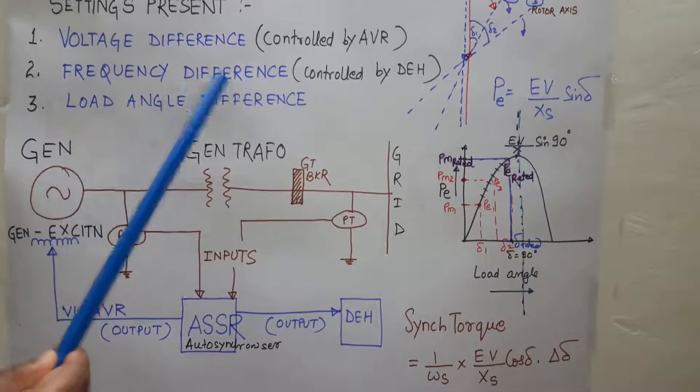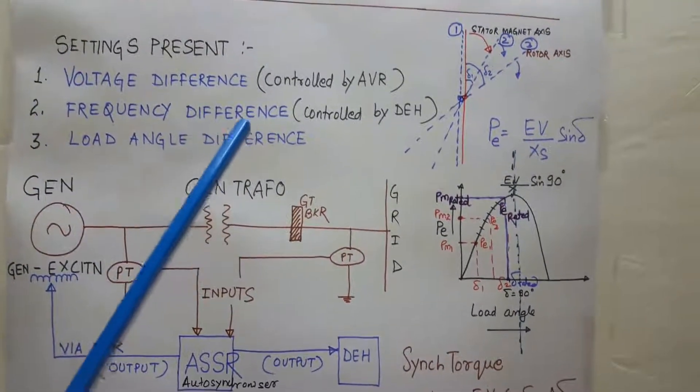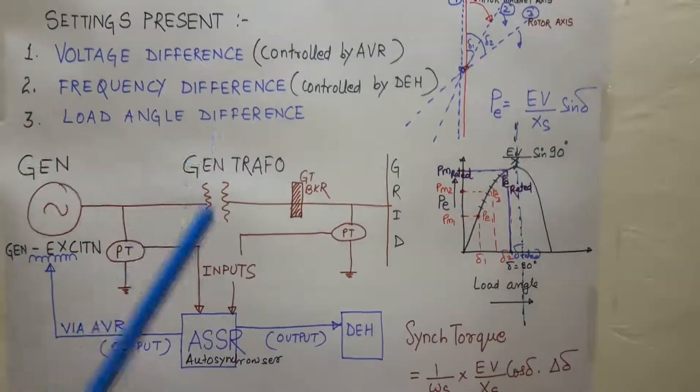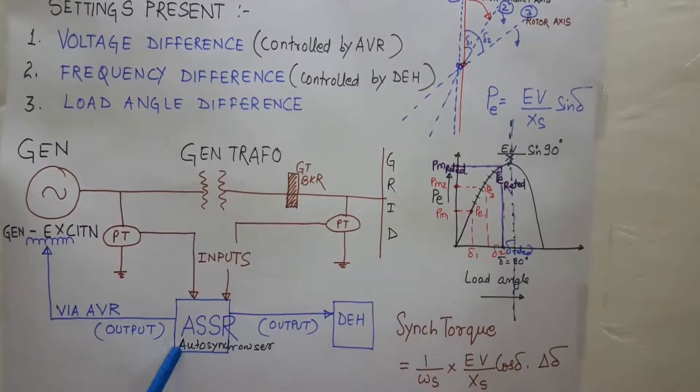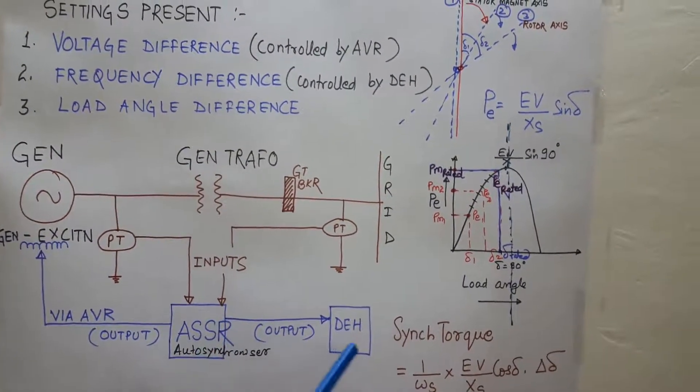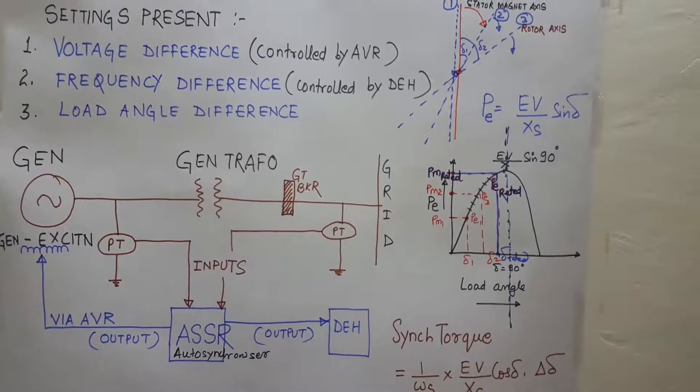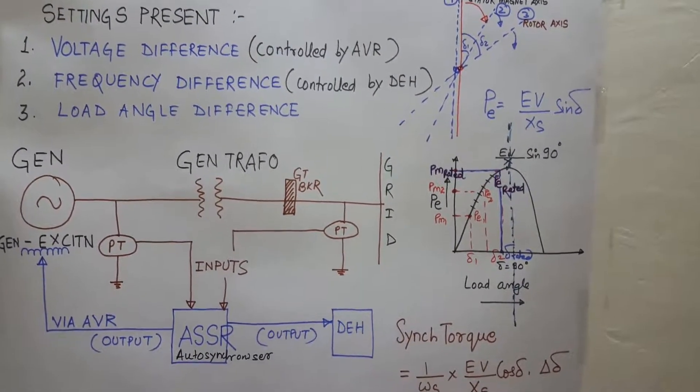And suppose if the frequency difference is outside the tolerance limit of the setting in auto synchronizer, then this auto synchronizer will send an output signal to the DEH of the turbine in order to control the speed of the rotor.